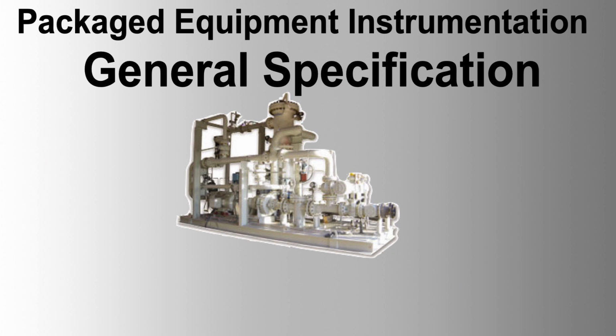Performance. The rangeability of the instruments shall be as specified in the attached data sheets, with errors expressed as a percentage of the calibrated span unless stated otherwise. The transmitter accuracy, including the combined effect of linearity, hysteresis, and repeatability, should be equal to or better than the figure stated in the attached instrument datasheet.